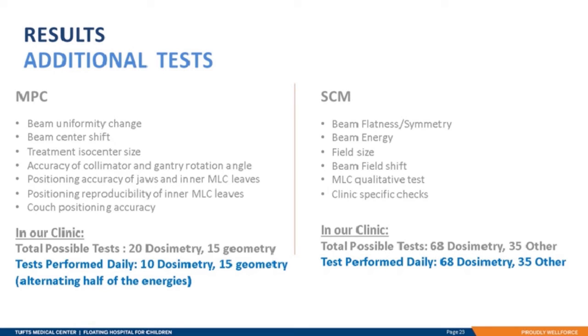While we use TG-142 as a base reference of comparison, it wouldn't be fair to not mention the other tests that these platforms do collect as part of the daily QA. Machine Performance Check performs many geometry tests and collects beam uniformity and center shift data. For our clinic, this translates to a total of 20 dosimetry checks and 15 geometry checks. Since we do choose to alternate the energy checks per day, of those 20 dosimetry tests, we perform 10 each day. However, the geometry checks are performed daily.